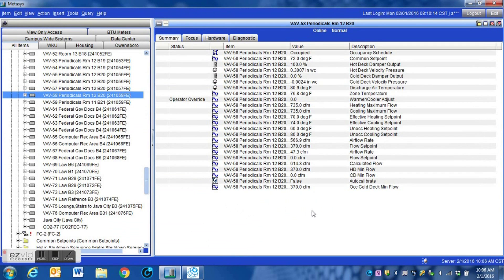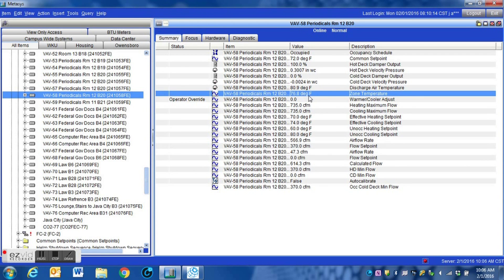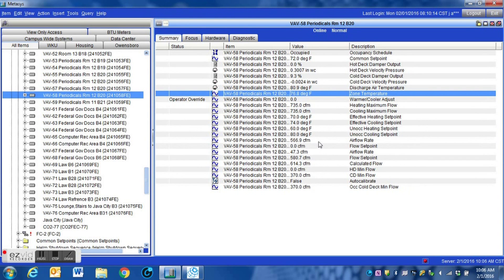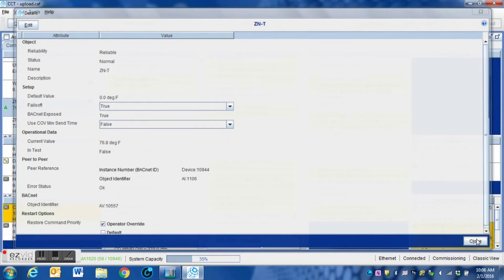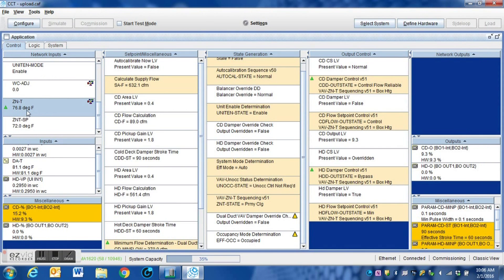Here we are. We are now reading the zone temperature from one thermostat and are sharing that information between two controllers. This can be used to share information between multiple controllers. If you have a few VAV serving one particular area, it's a great way to share data between devices.